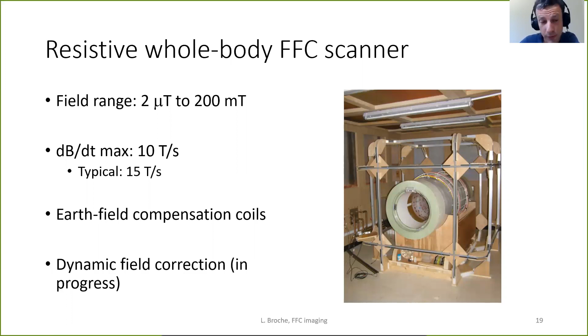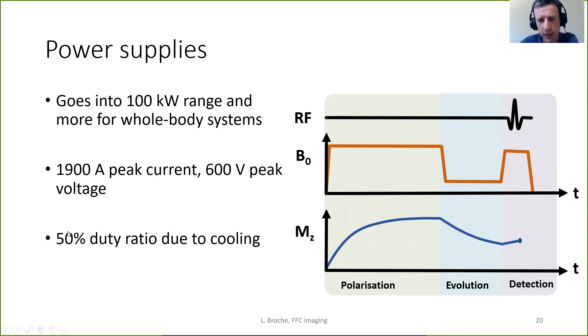Anyway, the biggest challenge with a resistive magnet for imaging is, of course, the power supply. As I say, you have to use very powerful power supplies, typically 100 kilowatts. The one we use can reach 125 kilowatts at full blast. And you need to have it very precisely controlled. So typically, when we reach 0.2 Tesla, we need 1900 amps. And when we ramp up and down, we typically need 600 volts. So that's quite high power. Because of that, we cannot use the scanner in DC mode. We need a 50% duty ratio to make sure that it doesn't overheat.